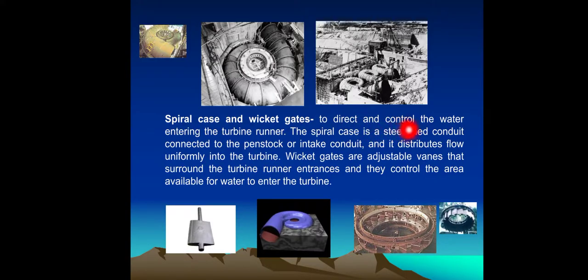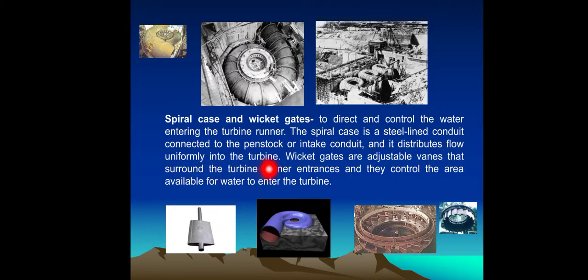Spiral Case and Wicket Gates: To direct and control the water entering the turbine runner, the spiral case is a steel-lined conduit connected to the penstock or intake conduit, and it distributes flow uniformly into the turbine. Wicket gates are adjustable vanes that surround the turbine runner entrance, and they control the area available for water to enter the turbine.